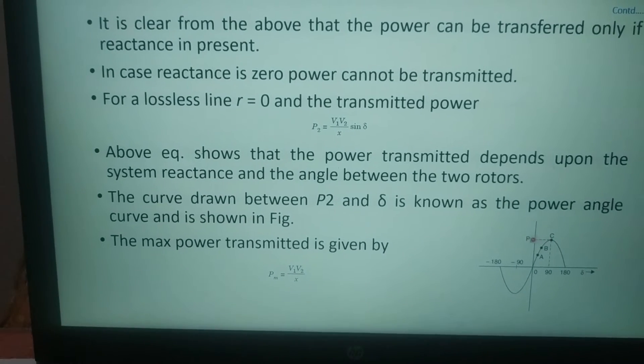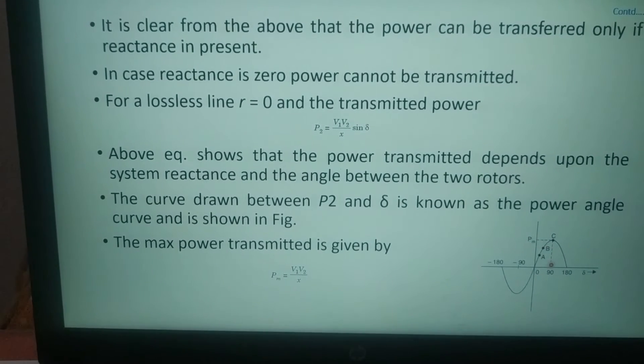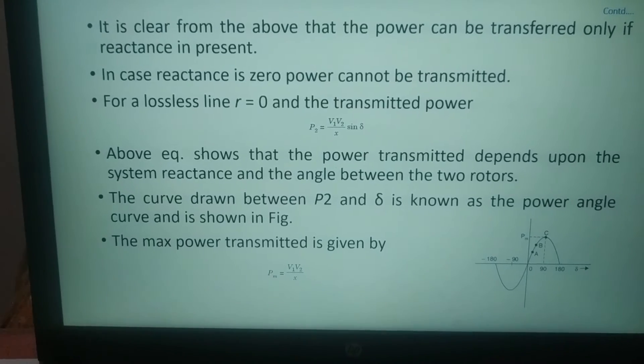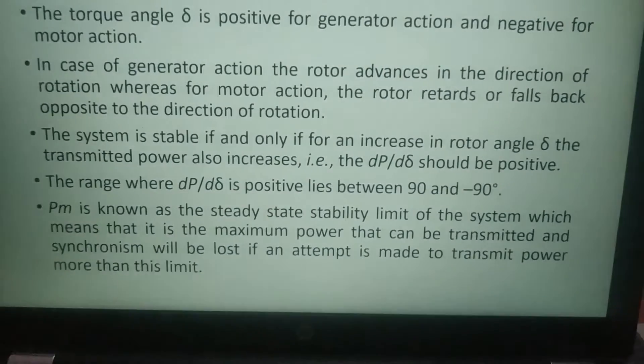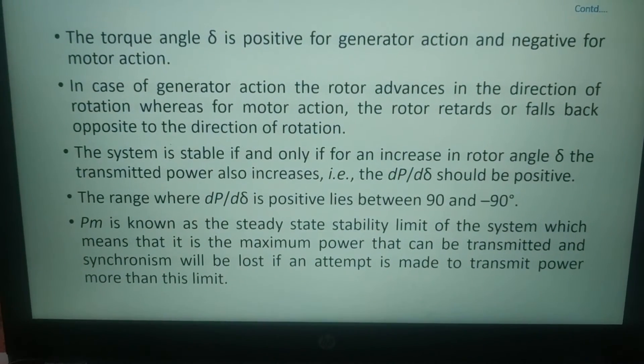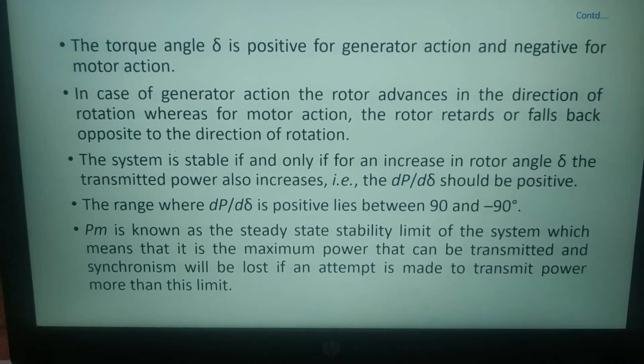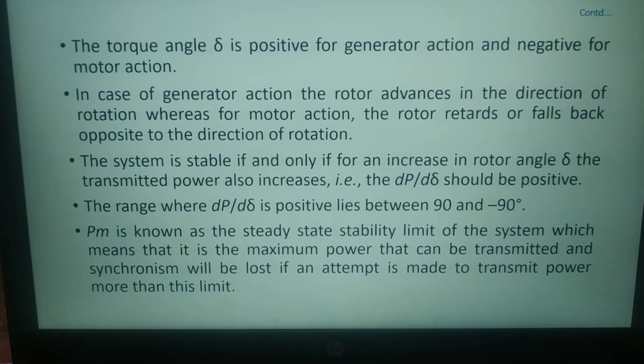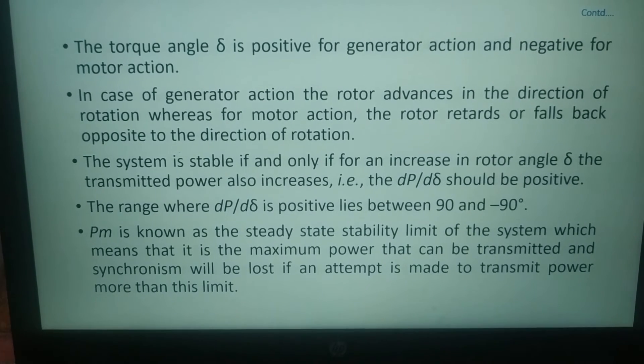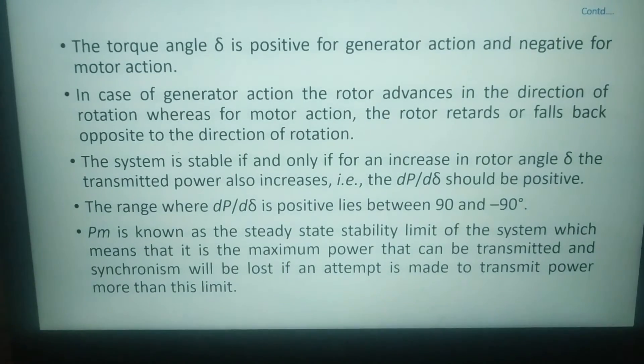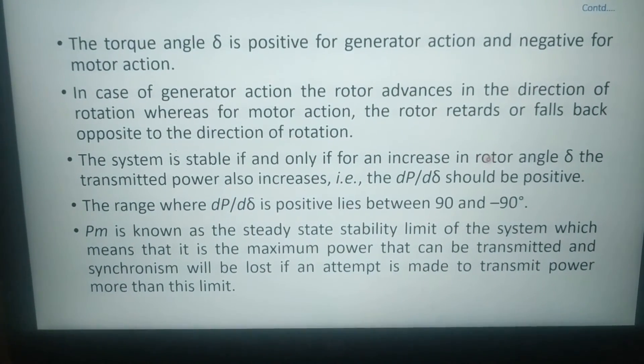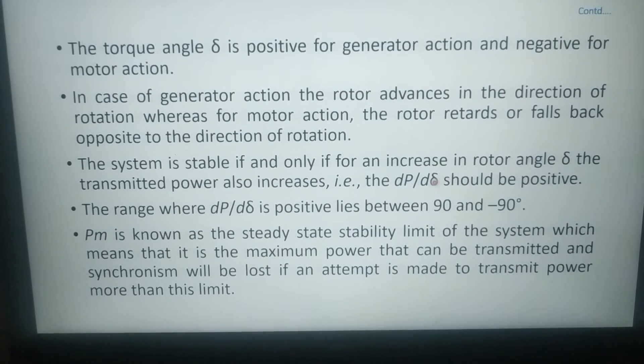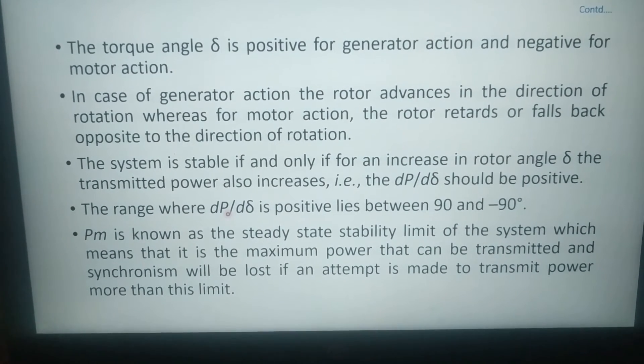This is the power angle curve. The maximum power transfer Pm occurs when delta equals 90 degrees and equals Pm equals V1*V2 upon X. The power angle delta is positive for generator action and negative for motor action. For generator action the rotor advances in the direction of rotation, whereas for motor action the rotor retards or falls back opposite to the direction of rotation. The system is stable if and only if for an increase in rotor angle delta, the transmitted power also increases — that is, dP/d(delta) should be positive.